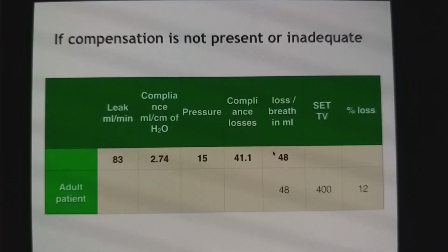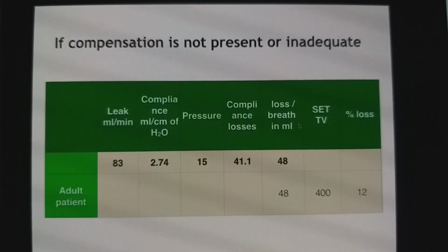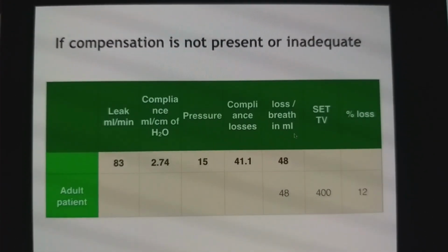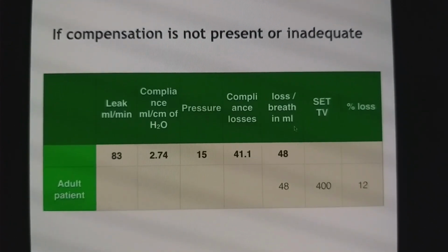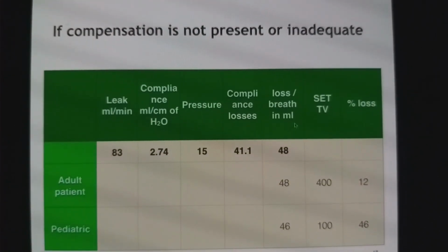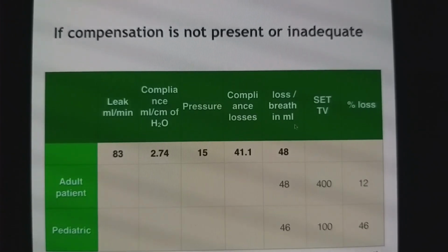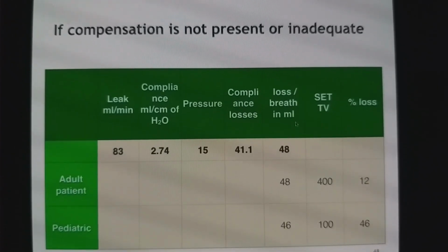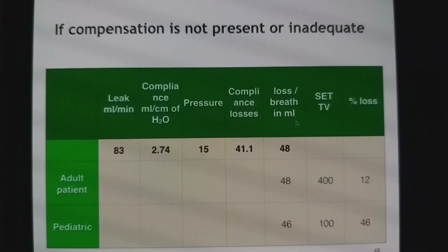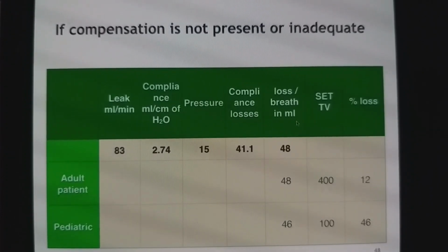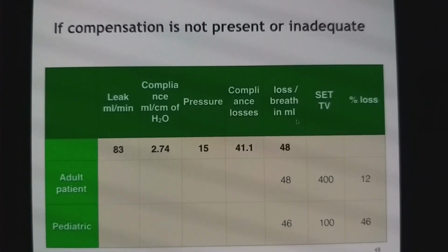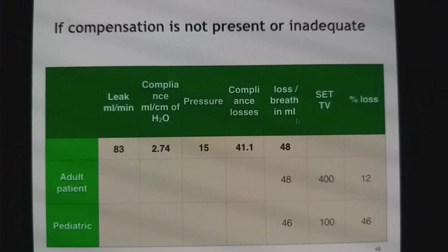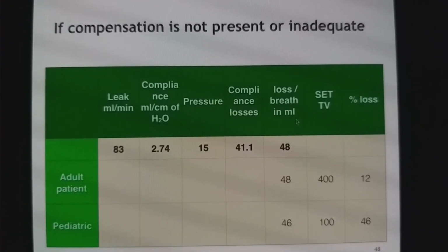Now in an adult patient it does not give you a big issue. It is only a change of 10% which you can compensate. But imagine that happening with a pediatric patient. You are losing almost 50% of the tidal volume. In fact, many of you might have noted that in spite of adequate tidal volume, many times your ETCO2 remains on the higher side in a pediatric patient if you have not done this compensation.